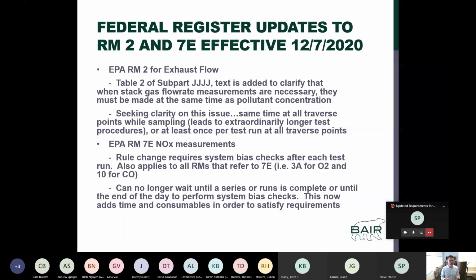I can tell you that on compressor engines, even if you're using the ASTM method and FTIR, you still have to do this check for 3A for your oxygen readings. And we never fail these checks on oxygen at the end of the day. In fact, we haven't had any issues. Method 7E, method 10, they're not technology specific, so you can run your calibration procedures using an FTIR analyzer under these methods, and given the stability of the FTIR analyzer, you just don't fail these system bias checks at the end of the day.